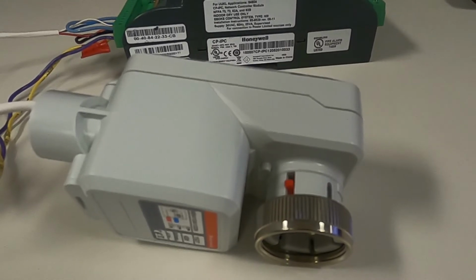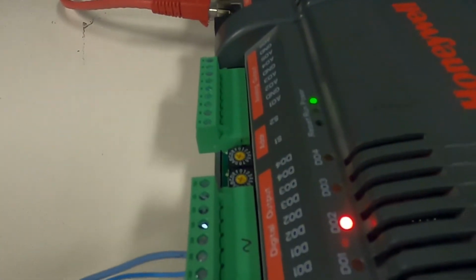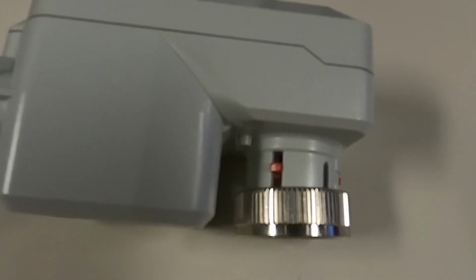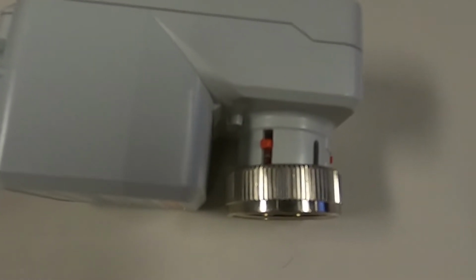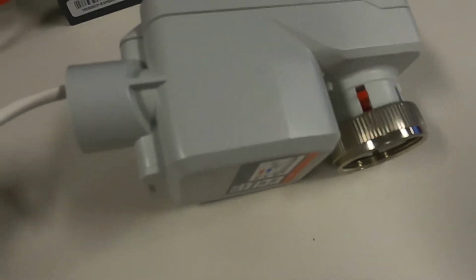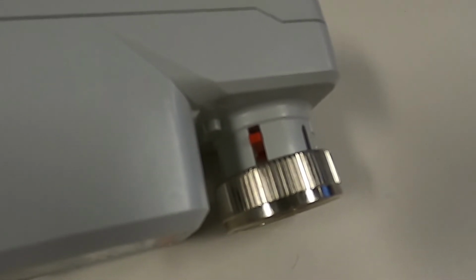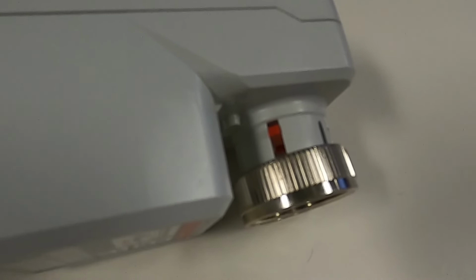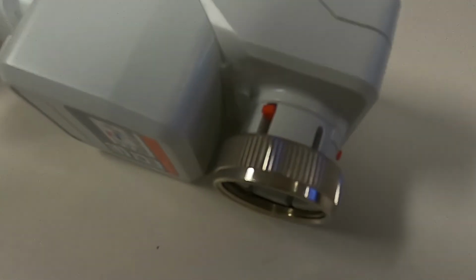So once I release this and say, hey, bring on DO2, which is currently turned on, this is going to bring that stem upwards. It is a long process. This actuator takes almost 90 seconds for a full-fledged up and down motion, so you can minutely see that. I'm not sure if I can capture it better in the video here though. So as you see, the stem is moving all the way up. And that's how a floating actuator acts as an analog actuator with two binary outputs. You can see the stem all the way up right now.